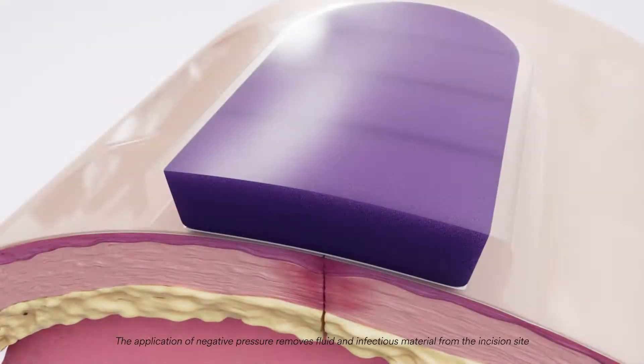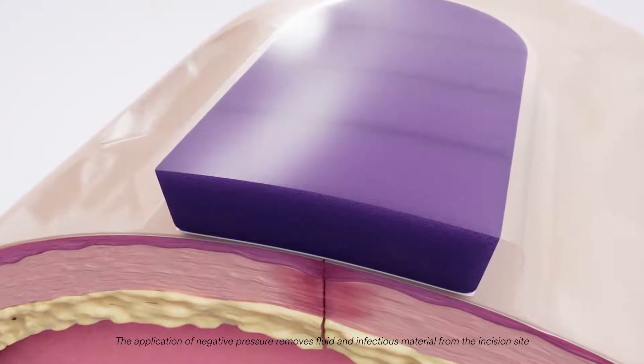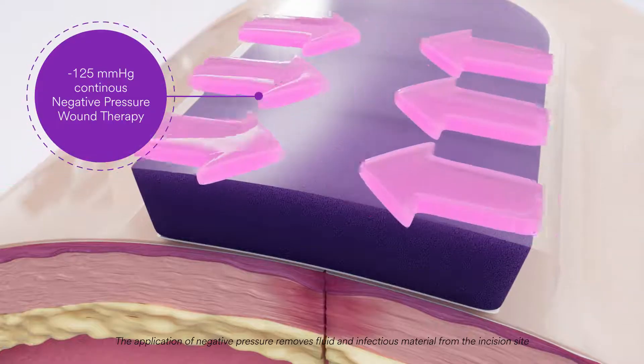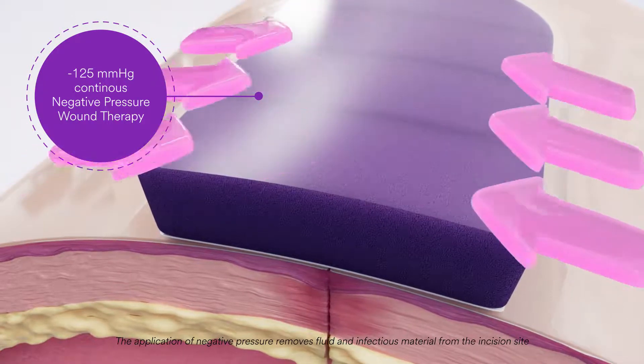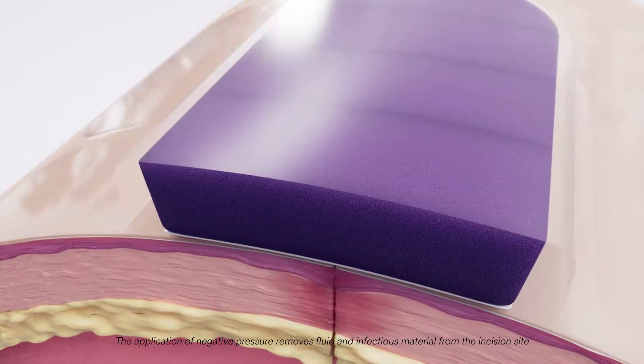The benefits of 3M Prevena therapy are not limited to barrier protection of the incision. The foam bolster is engineered specifically to manifold negative 125 millimeters of mercury continuous negative pressure wound therapy evenly across the incision, while conforming to the incision site.